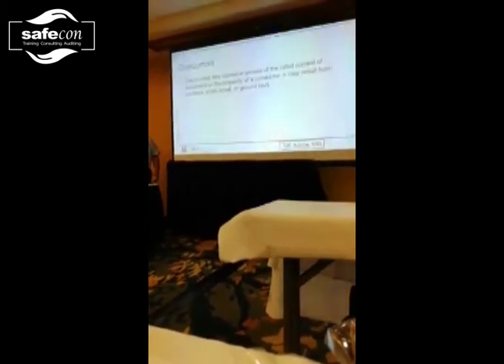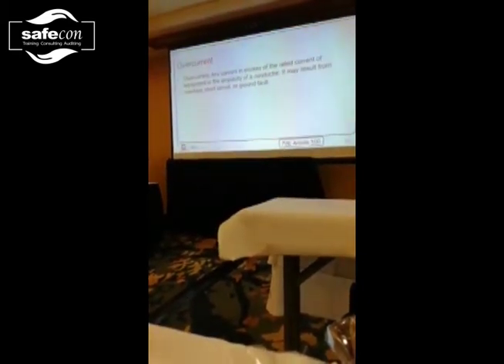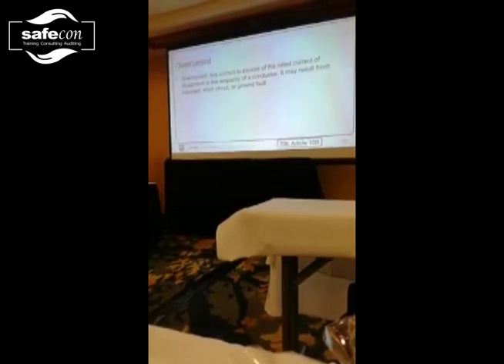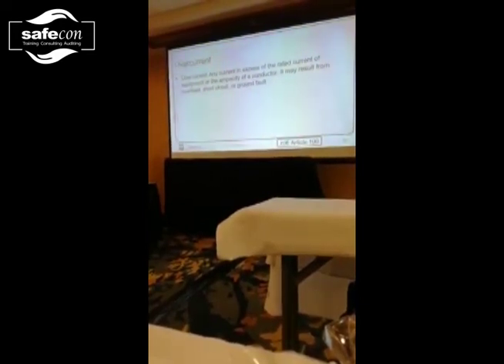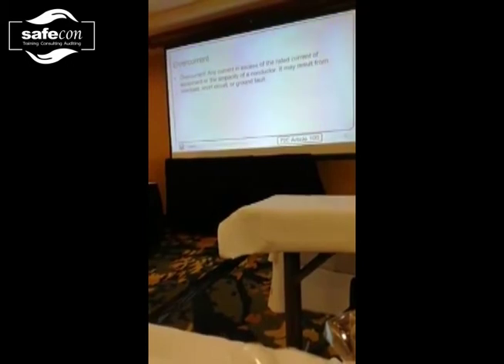So anyway, obviously the intent is to install equipment within its operating range. So when we get into Article 100, you'll see that the 70E committee took a step forward this time in defining available fault current and short circuit current, and they actually put a figure in this time to kind of identify where they really are. What we're concerned with is what is the fault current that's actually available at the point where we're working.